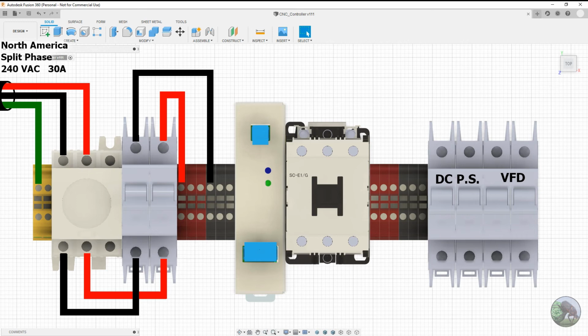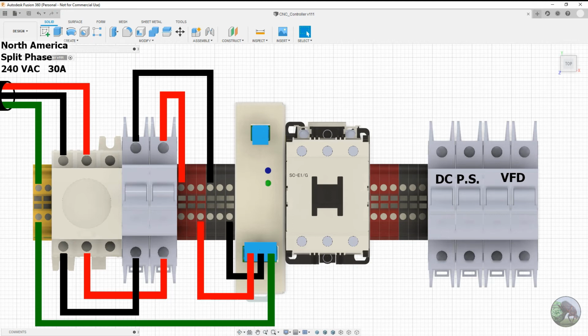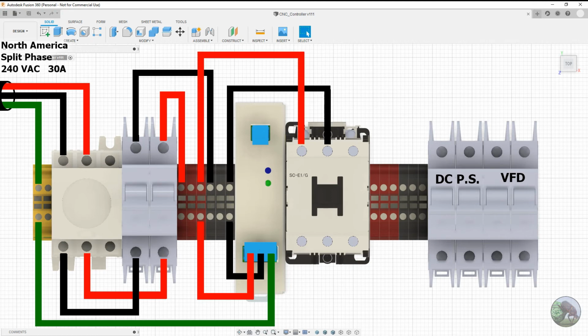And so out of this distribution block, we're taking power to this 24 volt DC power supply. This power supply gets its own ground wire going back to the terminal block. And then out of the same distribution block, power is going directly into the contactor. And so basically all the power that is consumed by the stepper motors, the controller board, and the VFD come through these 2 wires. And so this is what is being basically switched on and off when the contactor is either energized or not.